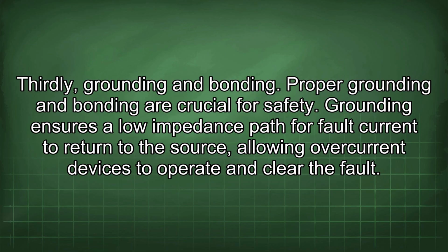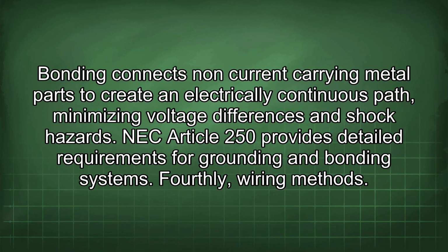Thirdly, grounding and bonding. Proper grounding and bonding are crucial for safety. Grounding ensures a low impedance path for fault current to return to the source, allowing overcurrent devices to operate and clear the fault. Bonding connects non-current carrying metal parts to create an electrically continuous path, minimizing voltage differences and shock hazards. NEC Article 250 provides detailed requirements for grounding and bonding systems.